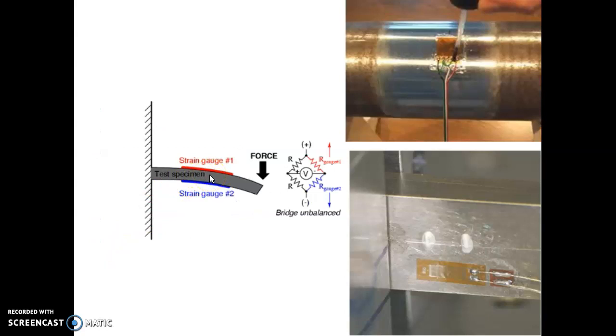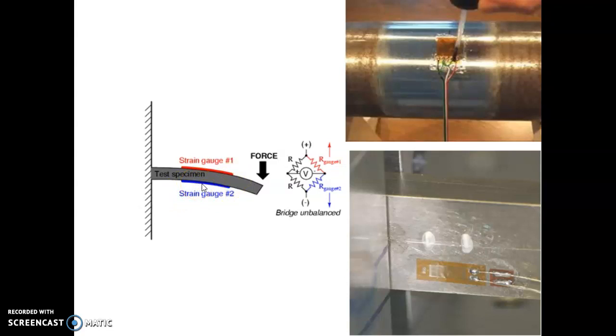Here is an example of using two strain gauges to measure force. A cantilever member has a force applied at the tip, causing bending. Two strain gauges are glued — one on top and one underneath the member. The top gauge (red) is subjected to tension and its resistance increases; the bottom gauge (blue) is subjected to compression and its resistance decreases. These are connected in a Wheatstone bridge, and the change in resistance is represented as a change in EMF on the potentiometer.